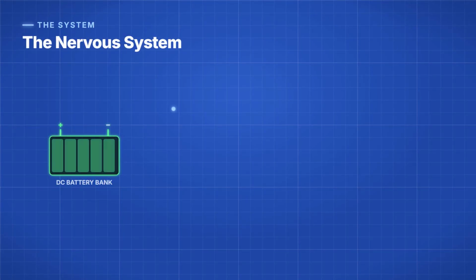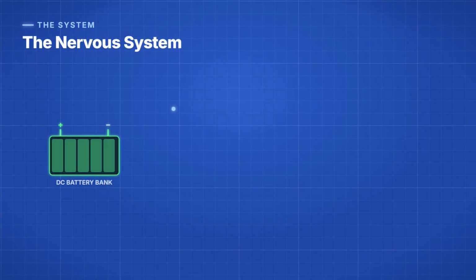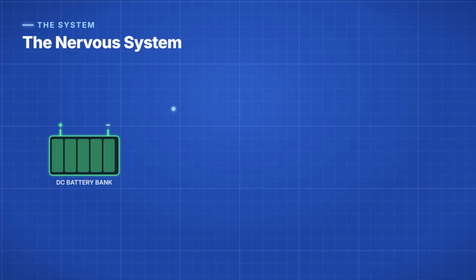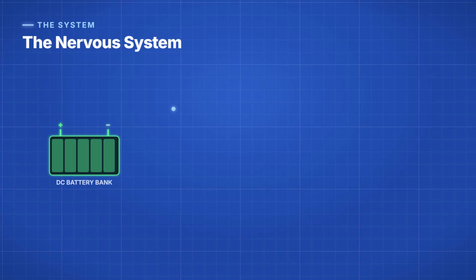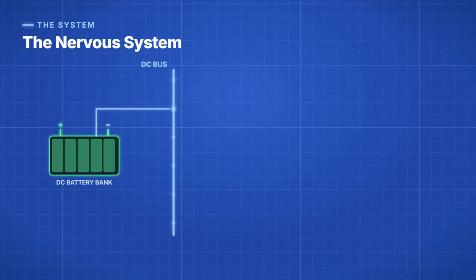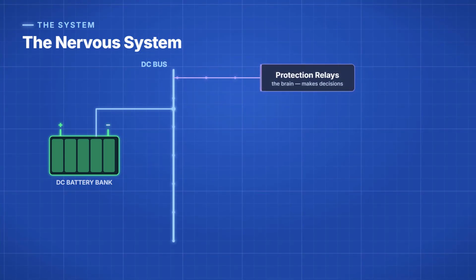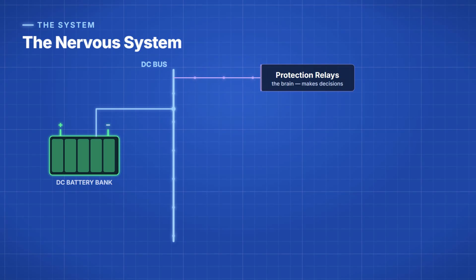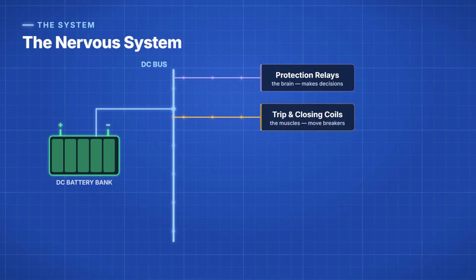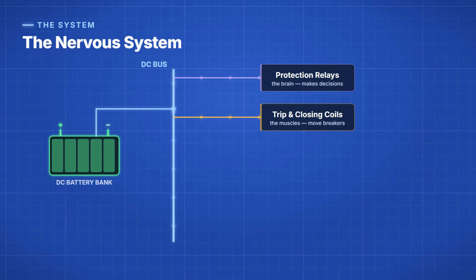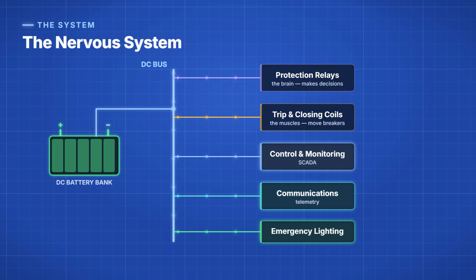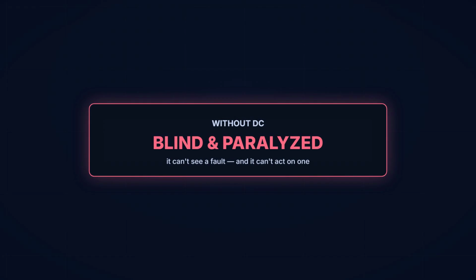So what exactly does this DC system feed? Think of it as the nervous system of the substation, quietly powering everything that has to keep working when the main supply does not. The battery connects to a common bar called the DC bus. From there, the power splits two ways. It feeds the brain, the protection relays that make the decisions, and it feeds the muscles, the trip and closing coils that physically move the heavy breakers. On top of that, it runs the control and monitoring, the communications, and the emergency lighting. Without DC, the substation is both blind and paralyzed. It can't see a fault, and it can't act on one.